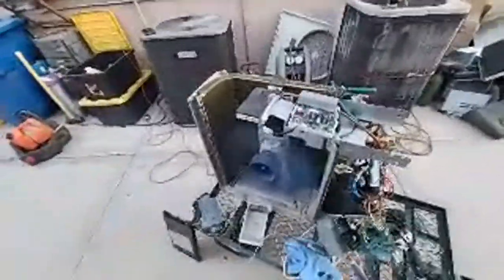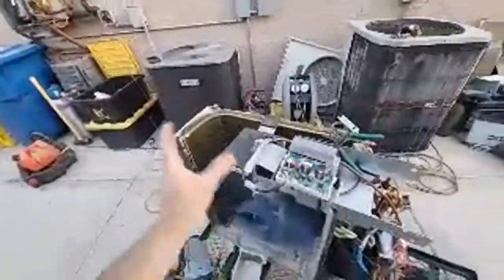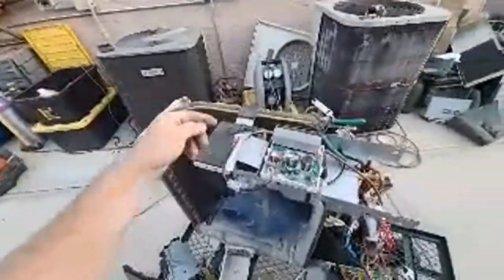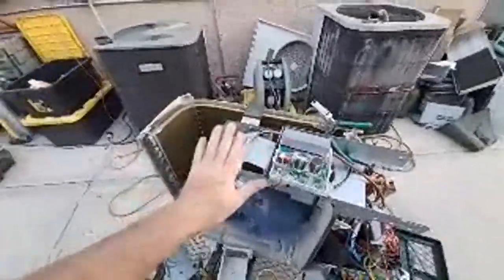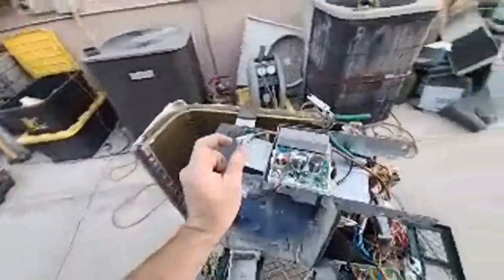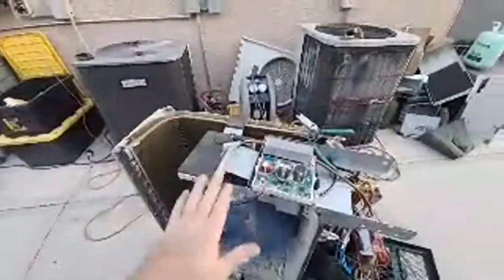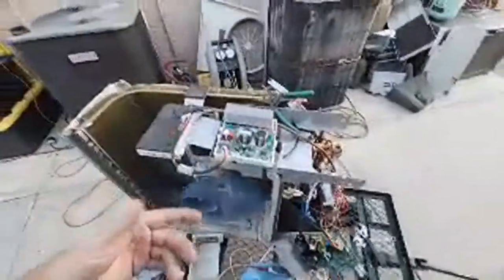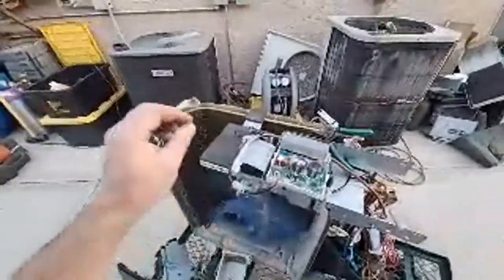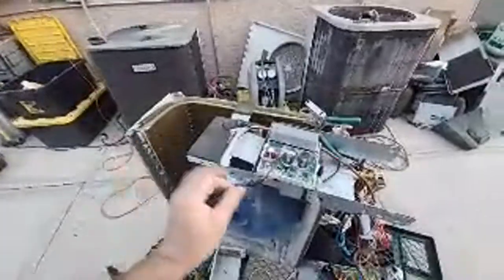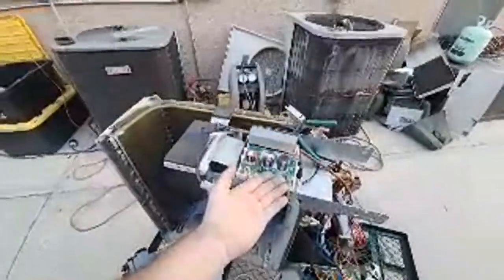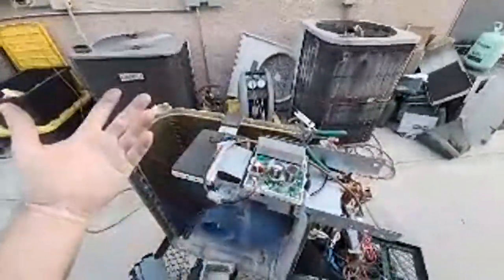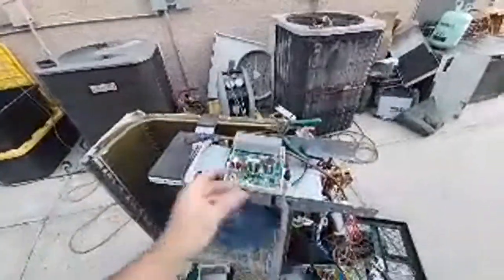But I think if I ever do it again, I'm going to do external rectifier, not going through my VFD. Probably just halfway rectify it like this. I got some flat diode, 220 packages or whatever they are that look like that, the 2-pin ones. I could actually mount on a heat sink in that unit, and just what I'll do is I'll go through a current limiting resistor to start getting the capacitors charged when they're dead charged, and then have like a 2-second delay on a relay that closes, and this will already be up to like 100 volts or so before it closes, and you won't get that first pow that you get.